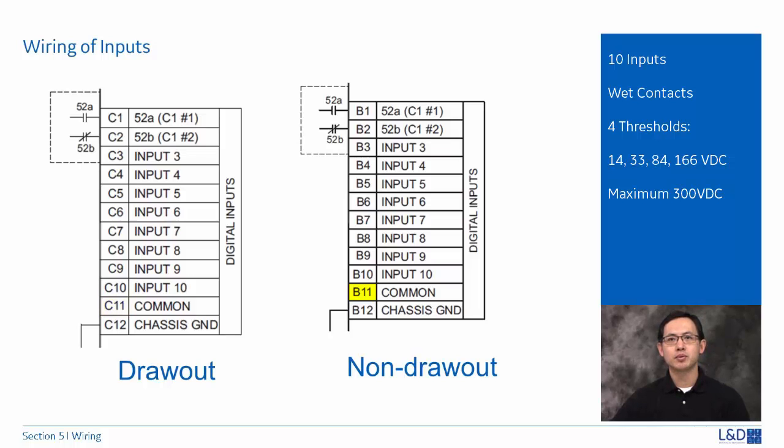The inputs can be programmed to different thresholds depending on the DC voltages. There are four threshold levels: 14 volts, 33 volts, 84 volts, and 166 volts DC. The maximum external source voltage for this arrangement is 300 volts DC.